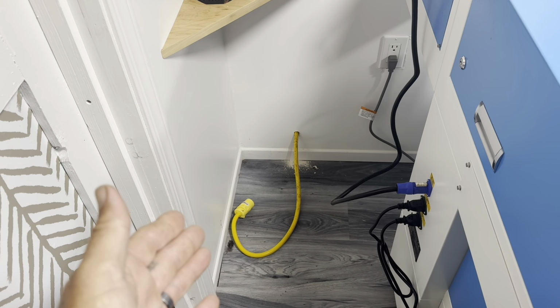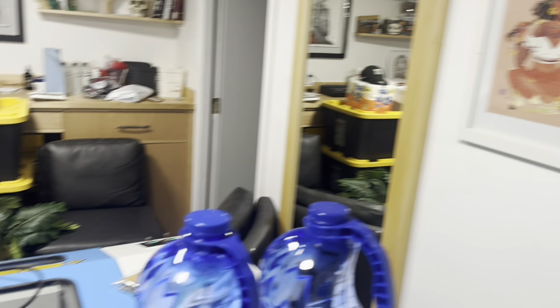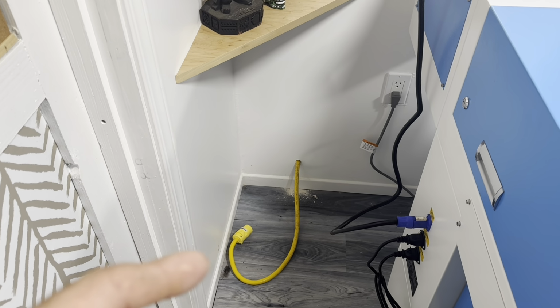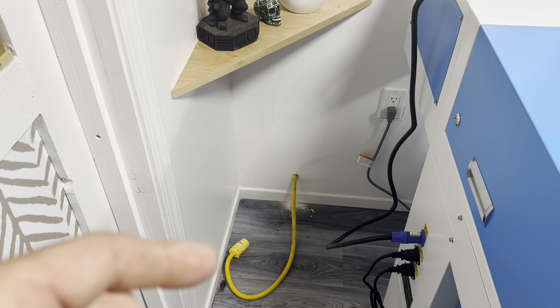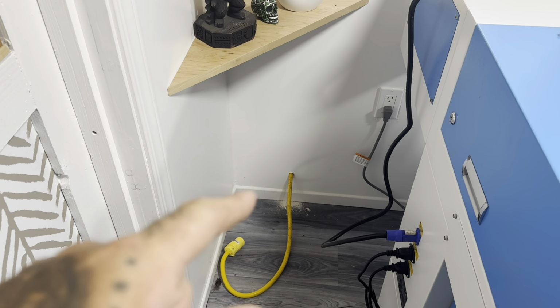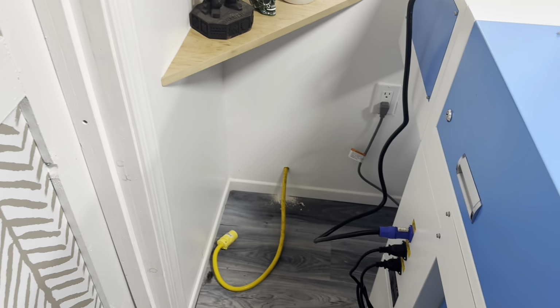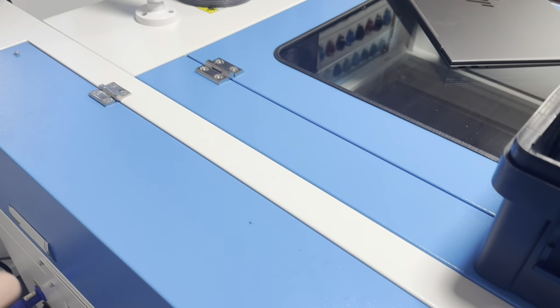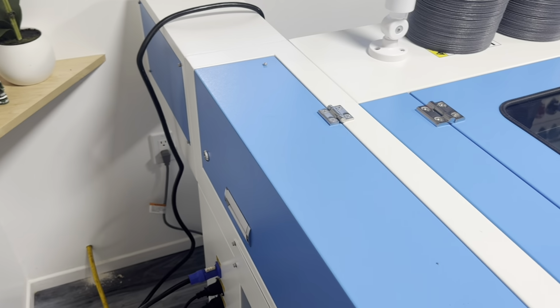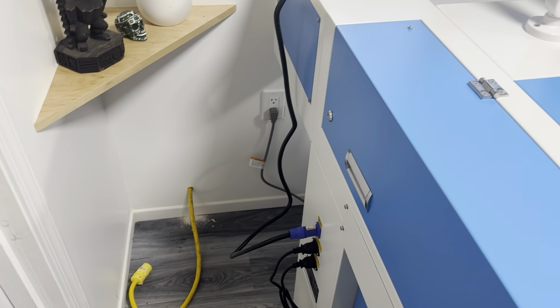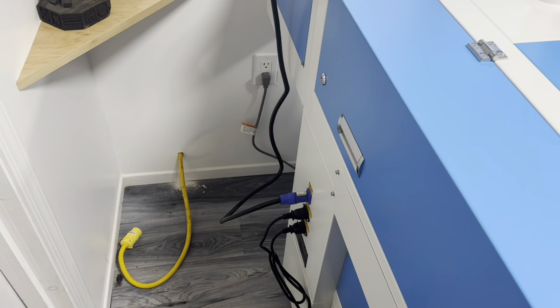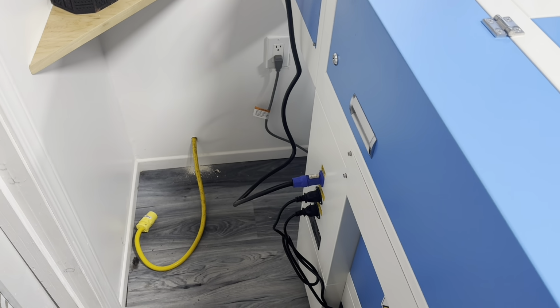So basically what I ended up doing is over by the pump house, I put in another outlet and I ran a wire from my breaker panel inside the house from a 20 amp breaker to that outlet. Then this extension cord plugs into that outlet. Then I brought it into here through the wall. Because this location is temporary for this laser. It may be here for 6 months, it may be here for a year, I don't know, but this is not going to be the permanent spot for it. So I didn't want to do anything too permanent as far as installation of this. So we have the plug now, we can continue with the setup.